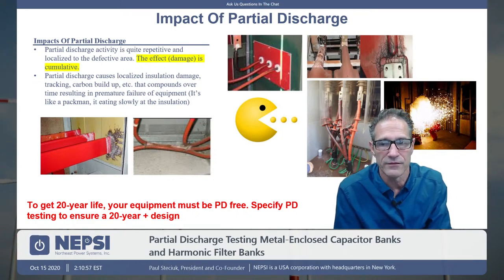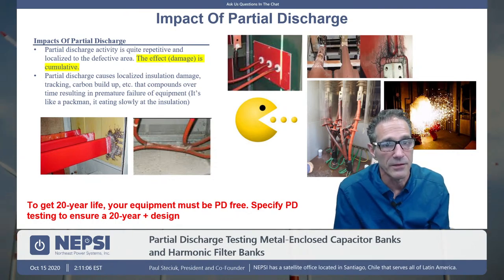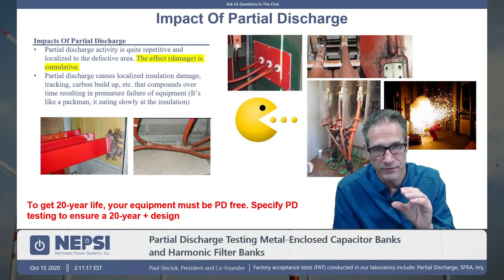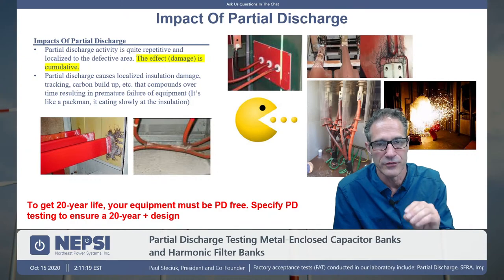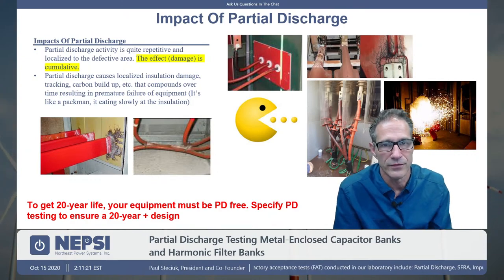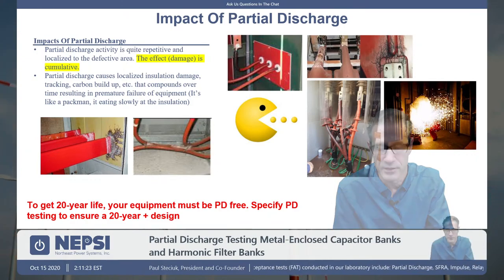Metal-enclosed cap banks and filter banks are all custom designed. Because of that, you want to test each and every design. So you type test, and we would also recommend that you consider making a production test. In other words, each and every design is tested. It's that repetitive partial discharge that occurs each and every cycle that in time will fail the equipment. And what happens is you get this type of activity going on as shown in these pictures.